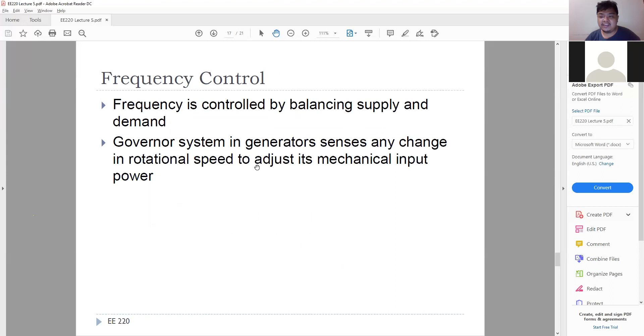So if the frequency decreases, so bumaba yung frequency, di ba? The governor will respond, yung governor control niya will respond by increasing fuel output unit until reference speed is obtained. Yung reference speed, yung frequency. So aakyat siya. Magbibigay siya ng additional power. Siyempre, kasi mababa yung frequency. Meron kang deficit. Droop mode ensures that the increase in fuel position is enough to prevent overspeeding when the system is returning to normal. Siyempre, kasi maraming generator, pwede mag-contribute all at the same time.